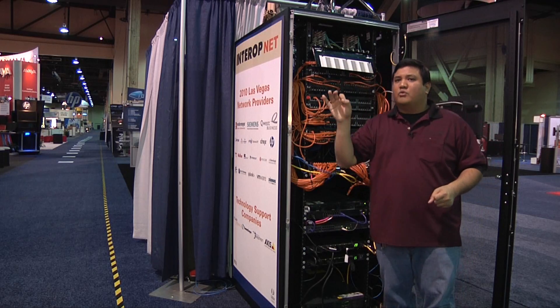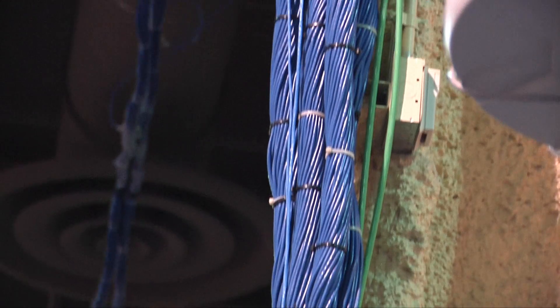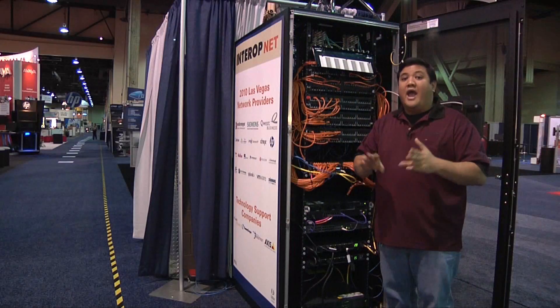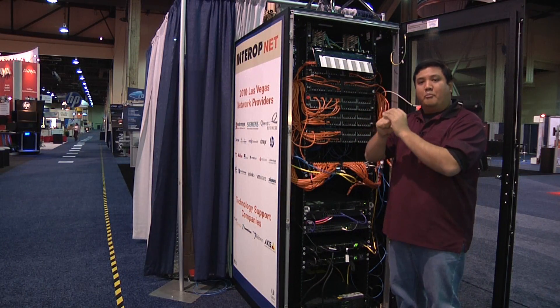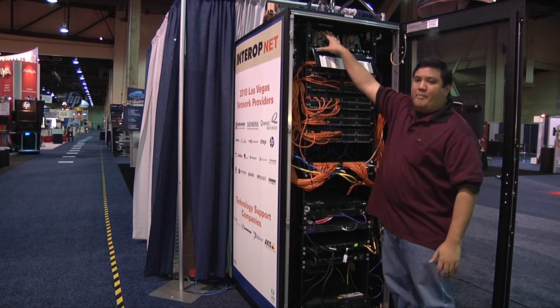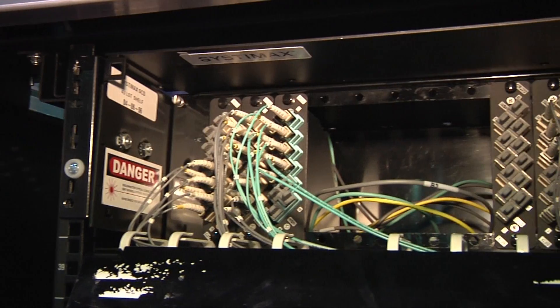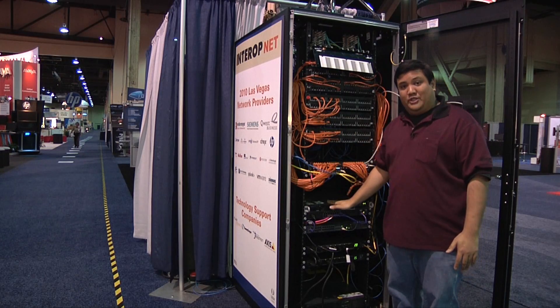You'll also see a smaller, what looks like a green cable — that's not actually cable, that's high density fiber. That gives us six pairs of single mode, six pairs of optimized multi-mode, and twelve pairs of multi-mode, all in one single bundle. If you look at the back of this chassis, you'd see that these modules have little bayonet connectors. Each one of those bundles plugs into the bayonet connector, and then that is patched in to each one of these switches.